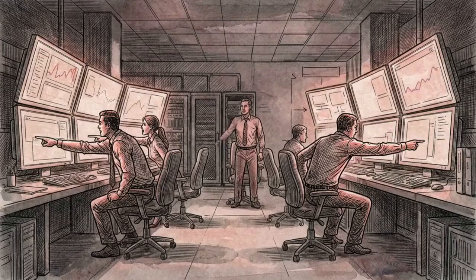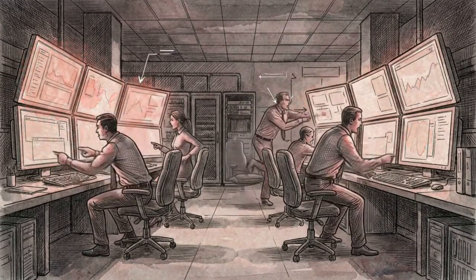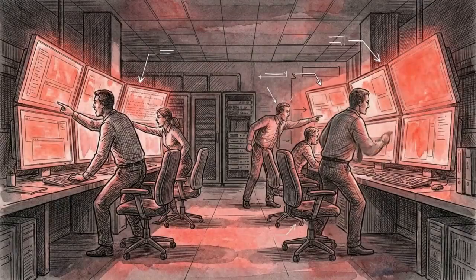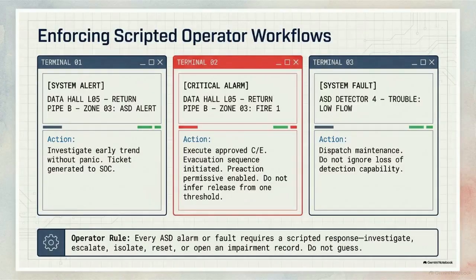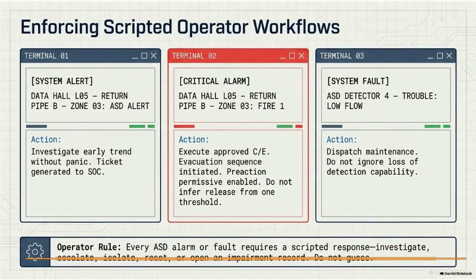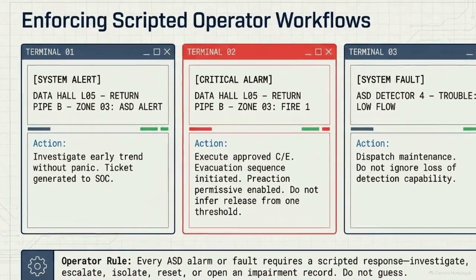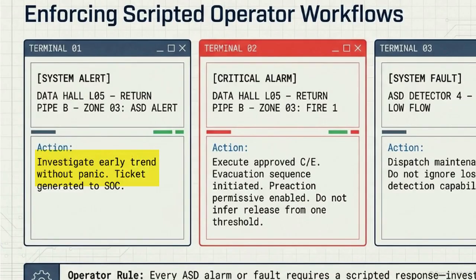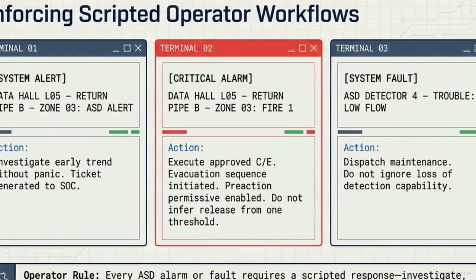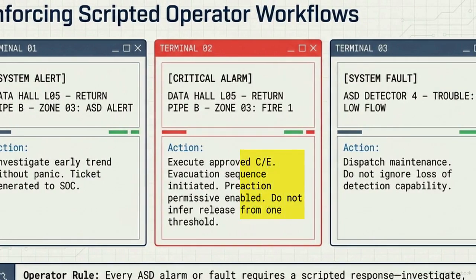When an alarm triggers at 3 a.m., the Security Operations Center is suddenly thrust into a high-pressure, chaotic environment. This interface map shows how we prevent panic by enforcing an absolute operator rule. Every system alert, alarm, or fault requires a pre-scripted response. Operators investigate, escalate, isolate, or open an impairment record. They never guess. Terminal 01 shows an early trend ASD alert, which prompts a calm investigation and a trouble ticket. Terminal 02 shows a critical fire alarm, which immediately triggers the approved cause and effect evacuation and pre-action sequences.